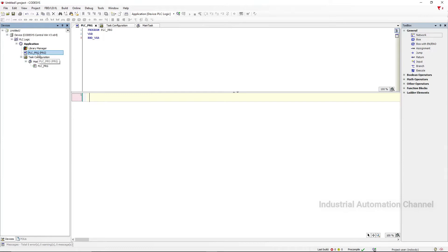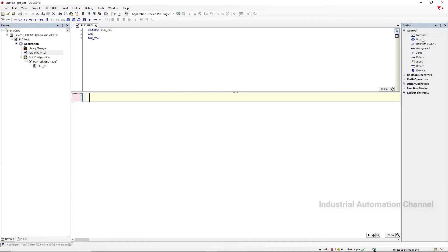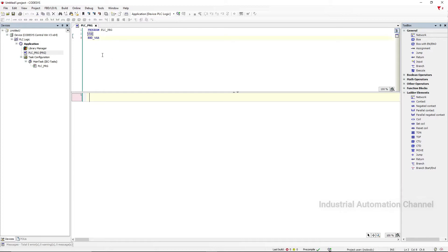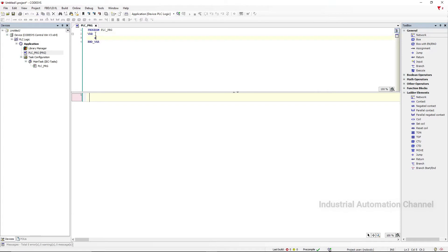Okay, let's talk about the main part of CODESYS. Since I have selected Ladder Logic as the programming language, the elements for this language are available here. You can select them and insert them to the project. The right side toolbox will give us all our operations including ladder elements. Hit the plus sign next to Ladder Elements. You can see we have coils, contacts, timers, counters, and other Ladder Logic tools. Here you see the variable declaration area. We have to declare the variables that we are going to use in our program. You can start by declaring the variables and then using them in the program, or you can start writing the program and whenever needed you will declare it. For example, I define a variable Start with the type Boolean.